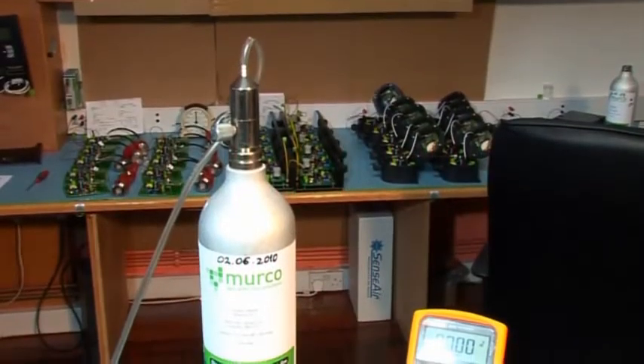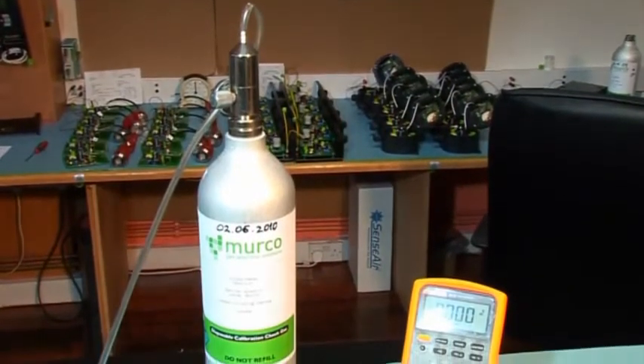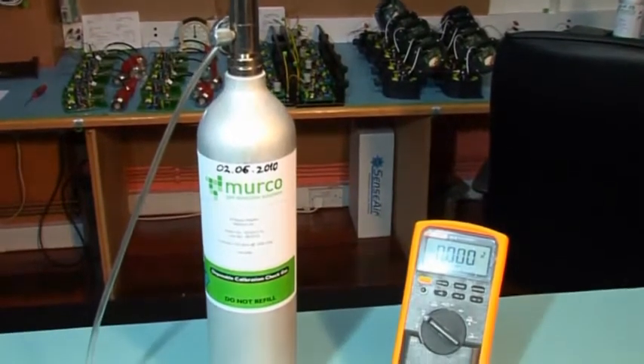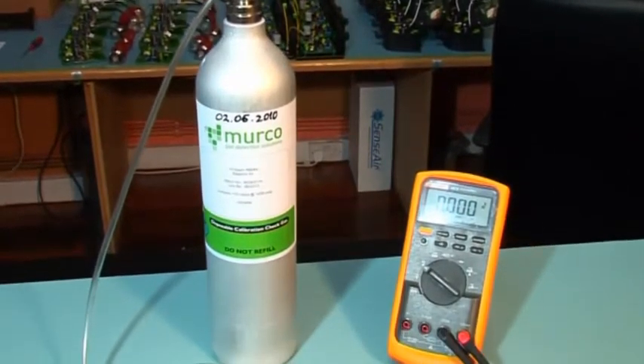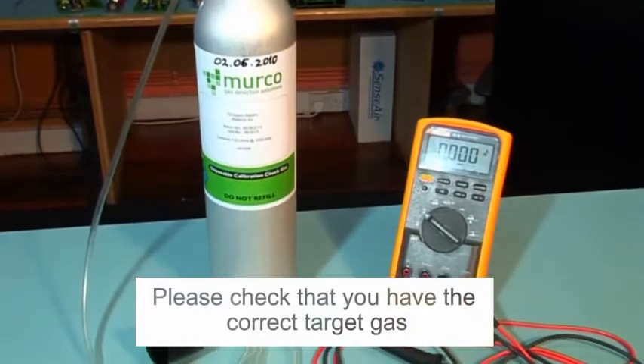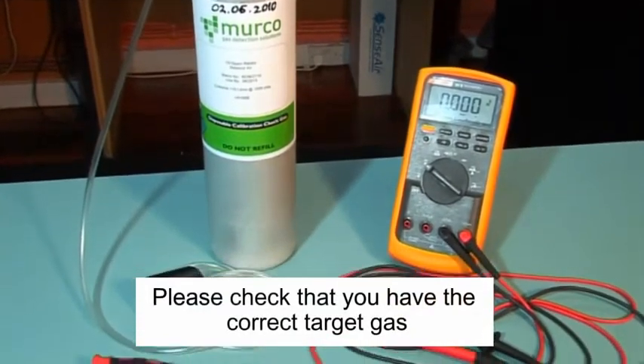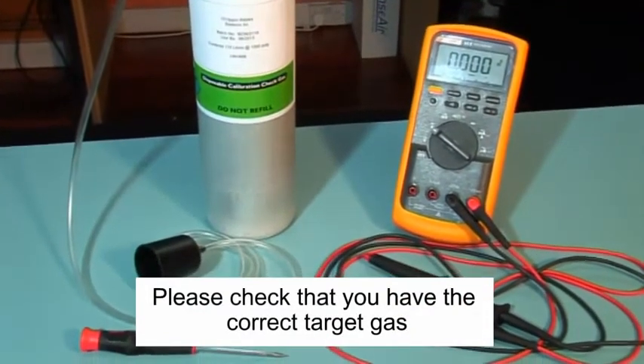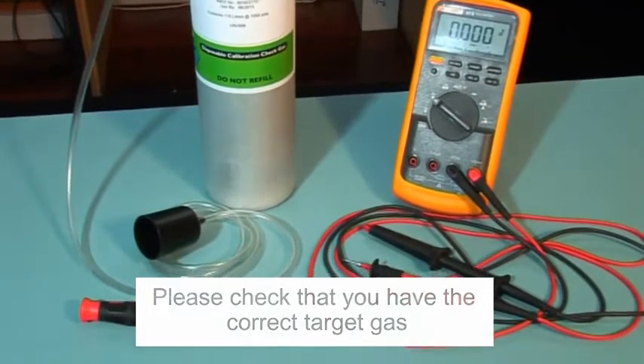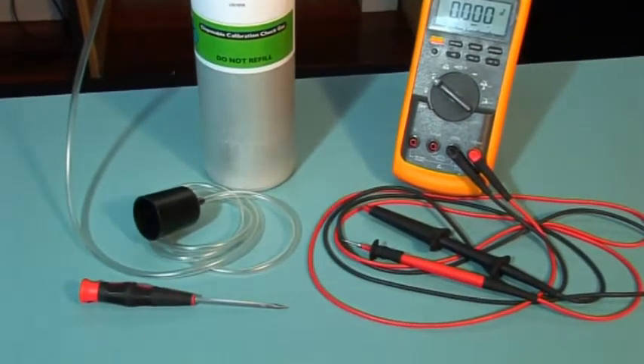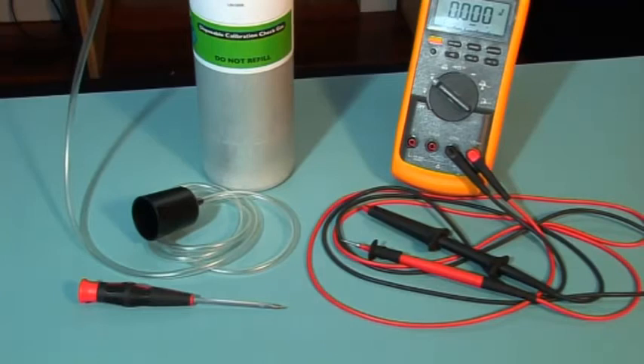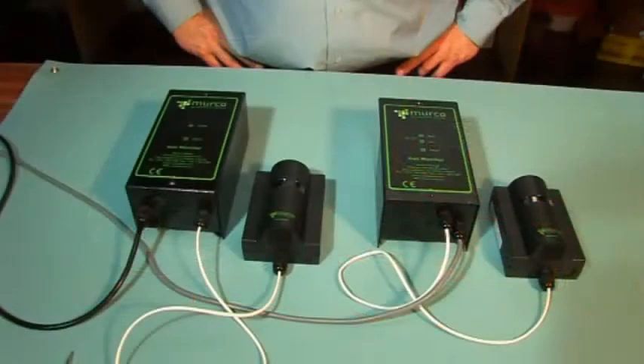The tools required are a digital voltmeter with a resolution to 2 decimal places, crocodile clips and/or a test probe, a flat-bladed screwdriver and a Murco calibration kit, which includes your cylinder of calibration gas, flow regulator, flexible non-absorbent tubing and a vented calibration hood. This is the MGD unit.